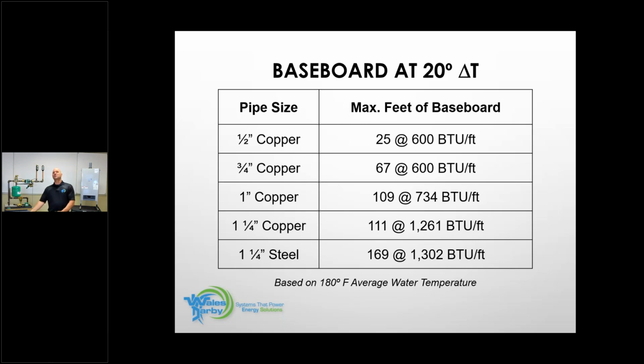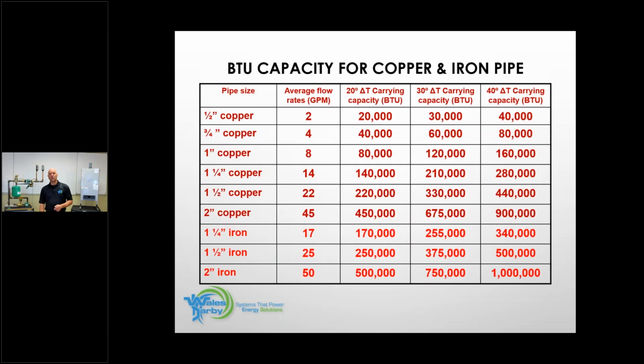This is what we use daily. These are the pages that we use on a daily basis, obviously not in the middle of summer, but during heating season, when guys call and ask, this is what we live by. If I have 80 feet of baseboard on that heat circuit, I am going to use up the ability to put 600 BTU of heat energy into the home per foot of baseboard, per linear foot of baseboard. So just keep that in mind when you're designing and sizing.